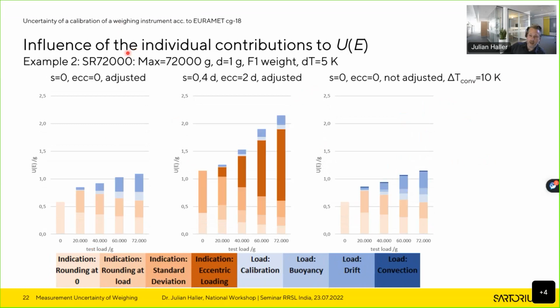So if you have a look at, let's say, a higher capacity weighing instrument with a maximum of 72 kilograms and a scale interval of 1 gram, we would then use F1 weights, that is sufficient. And if you again look at these 3 different examples, you see that the weights, the blue parts, play a much less important role for the calibration uncertainty of this instrument. Rather, the complete uncertainty is dominated by especially the rounding, it's a rather coarse instrument, and also, of course, by the standard deviation and the eccentricity, if you measure that respectively. So the weights are not that important, even although we just use F1 weights in this example.